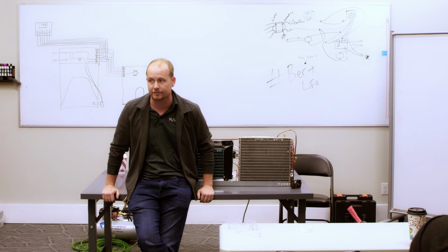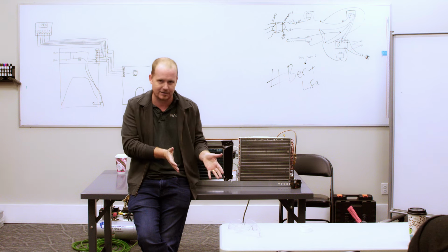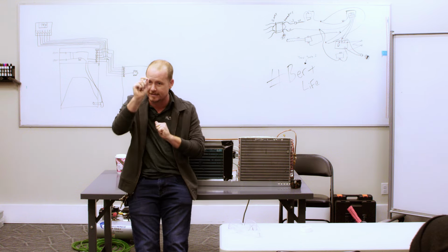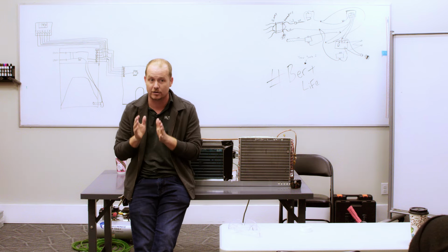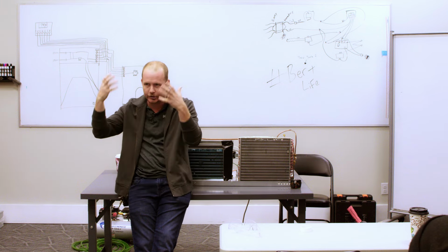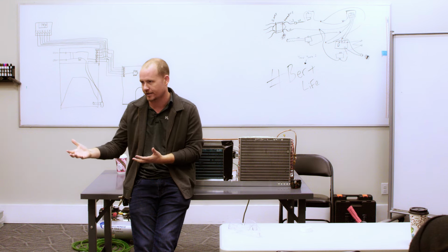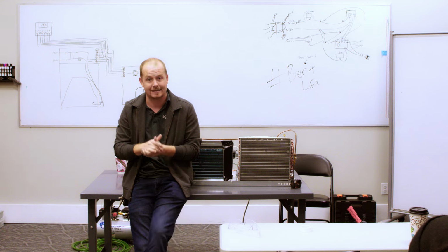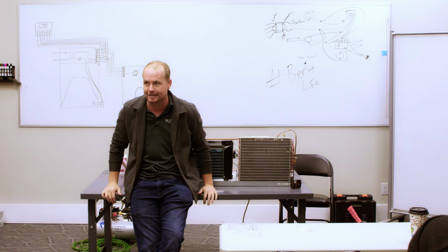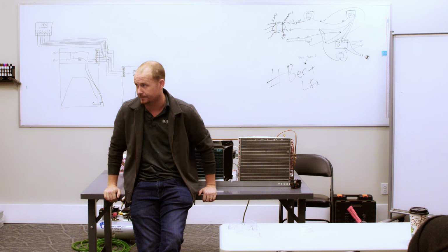Now again, when I throw around rules of thumb, you take them with a grain of salt, and in comparison with manufacturer specifications. Jessica's really good at looking at manufacturer specifications. So if you want to see somebody who's really good at looking at the panel and seeing what the manufacturer says, she's really good at that, and that is a really important trait. And it's also good to then take that and compare that to some good general rules of thumb knowledge to help with diagnostics. Because it's not all about just charging, kind of like what Matt and Aaron both said. It's not all just charging. You start with solid visual inspection, looking at your coils, just making sure that everything's clean and in good shape before you even begin with adding charge, especially to an older unit.